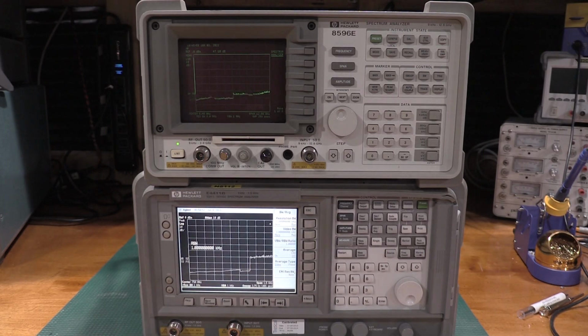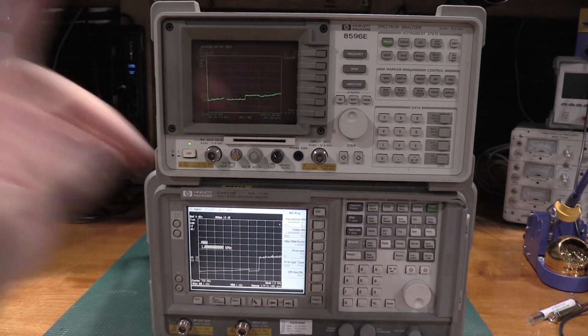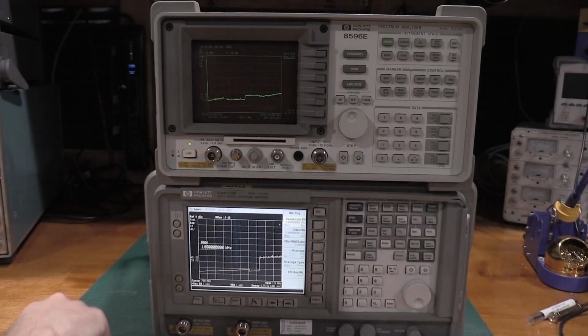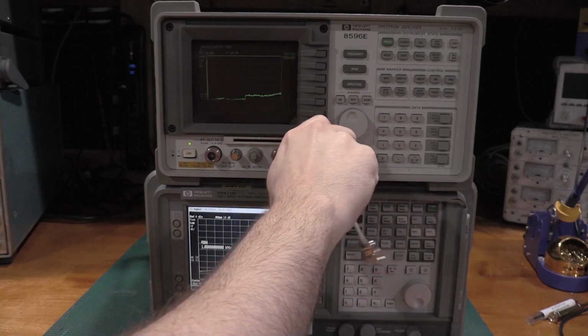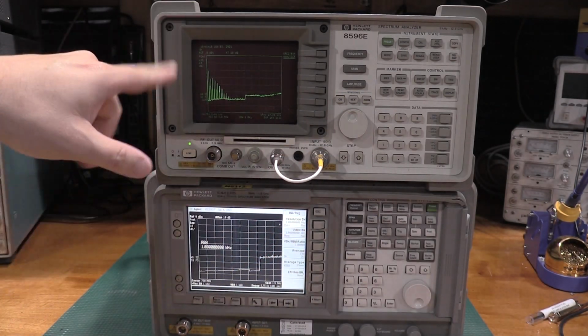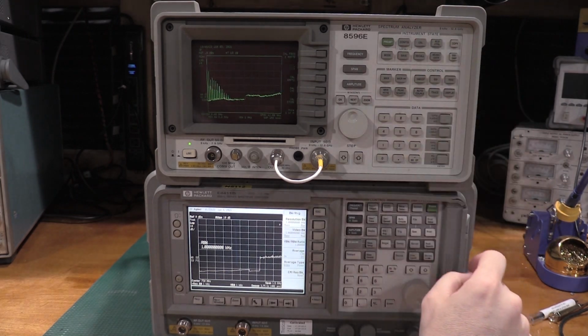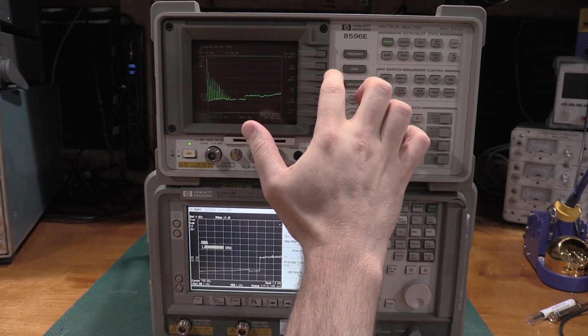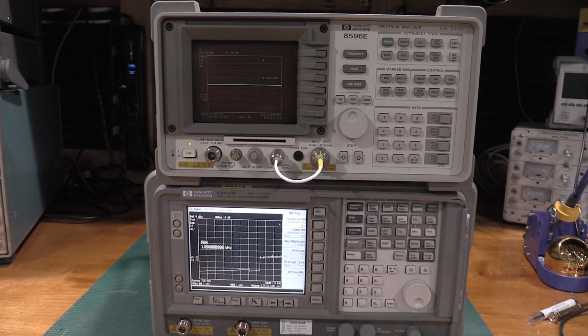Now, there's going to be 3 calibration routines for this. There's going to be frequency, amplitude, and YIG. This has a YIG tune filter in it. So when I have to do the YIG tune filter, I'll actually be using the comb out. But to start, so we have some power. Cal, amplitude, and frequency. And it's now going to go through some stuff. I won't sit here and bore you guys with it, so I'll just leave it go at the moment. But I'll bring you back when it's time for the YIG, or if there's any problems.